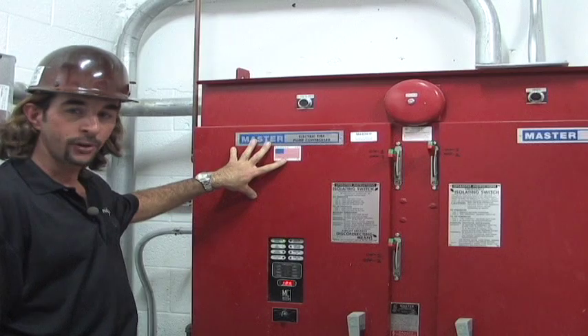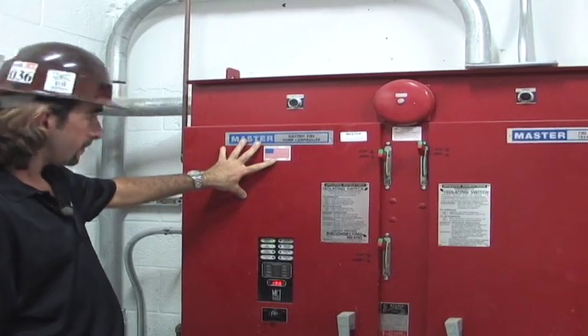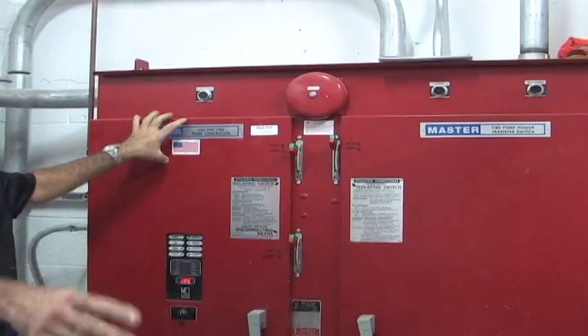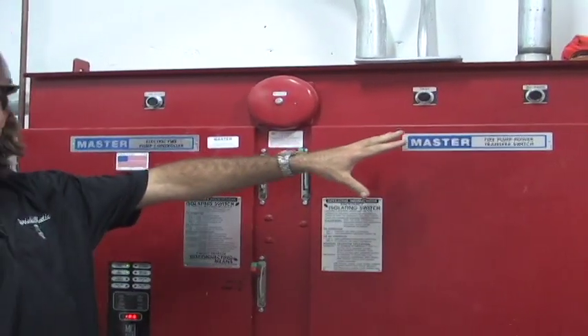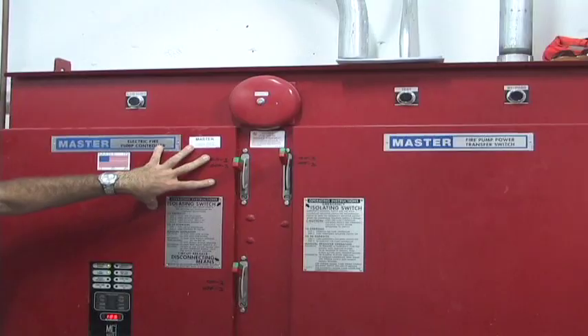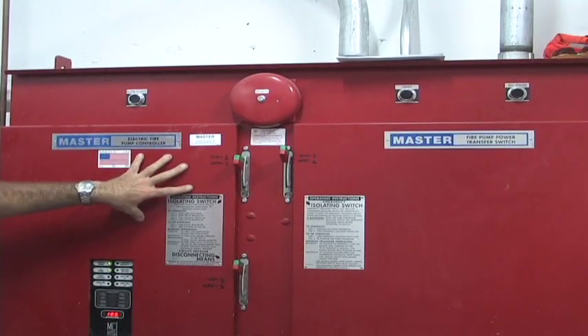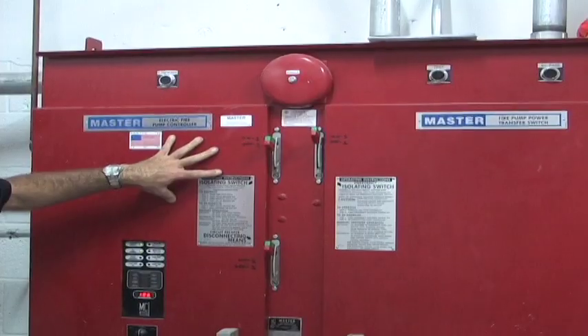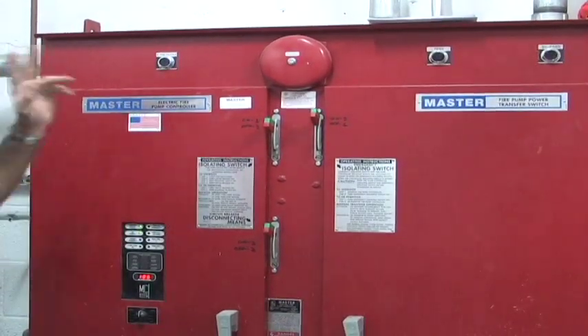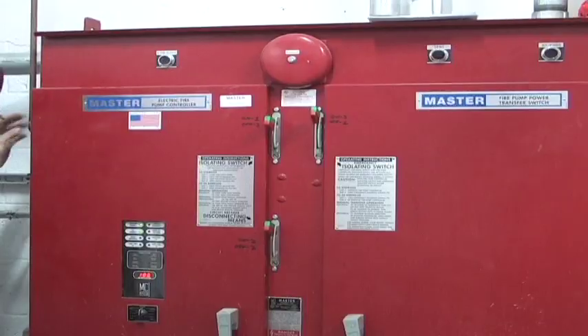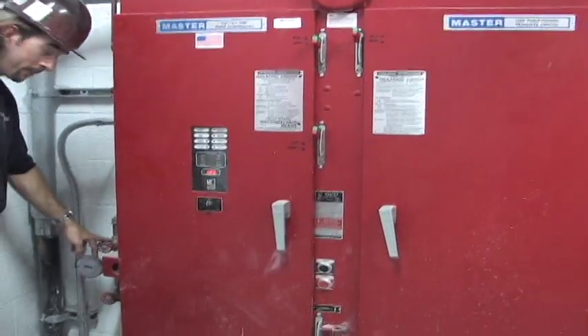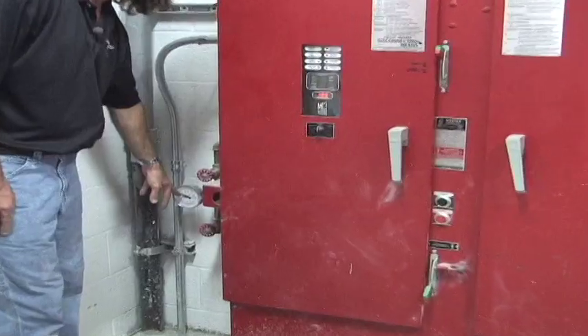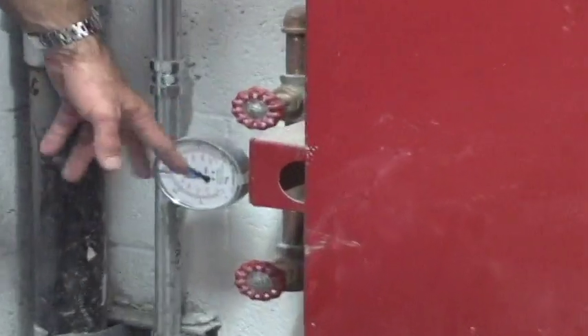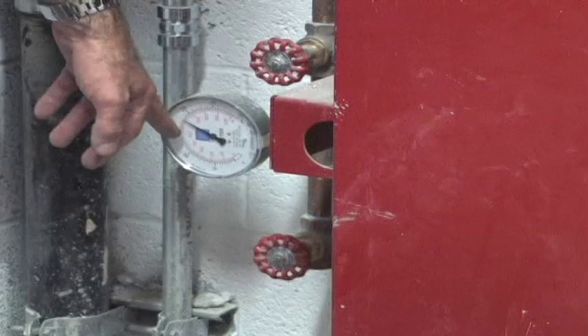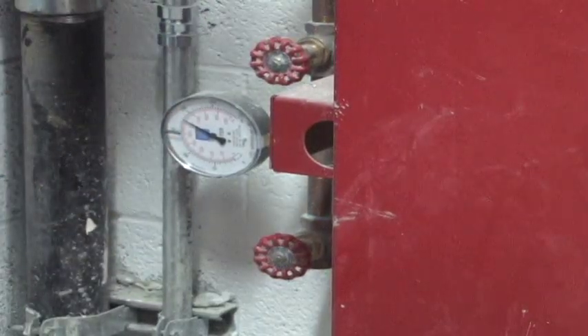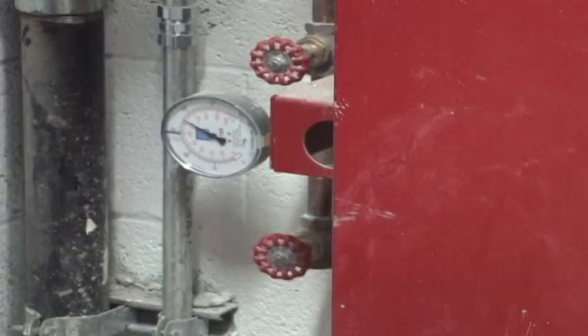This is our fire pump controller right here. This is going to strictly work just the fire pump. Just as the jockey pump works itself, the fire pump has its own pressure switch in it also. It can also be run manually, or it can be started with loss of pressure. Also, like the jockey pump, we have the brass half-inch line, which is our sensor line also. I've got a mark on our pressure gauge at 150 psi. As we open up that bottom valve and the needle drops down to 150, we will have an automatic loss of pressure start of our fire pump.